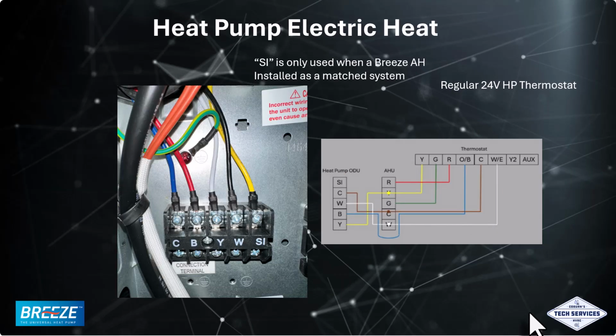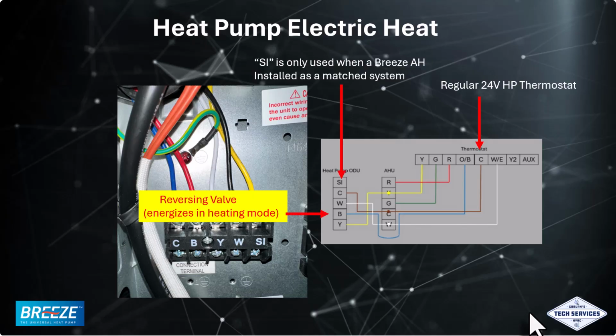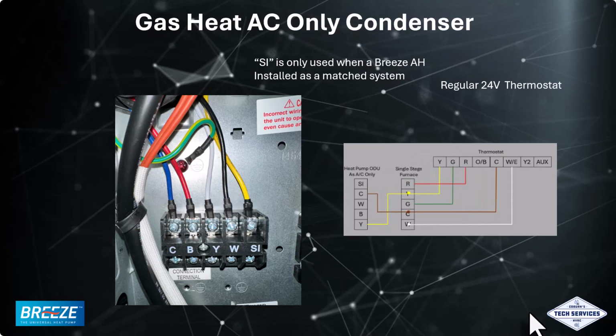Heat pump with electric heat. You need a typical 24 volt heat pump thermostat, and you will wire the B terminal from the thermostat to the B terminal on the outdoor unit. These units reverse in the heating mode, so the valve would be energized in heating. Y and common. Gas heat with AC condenser.